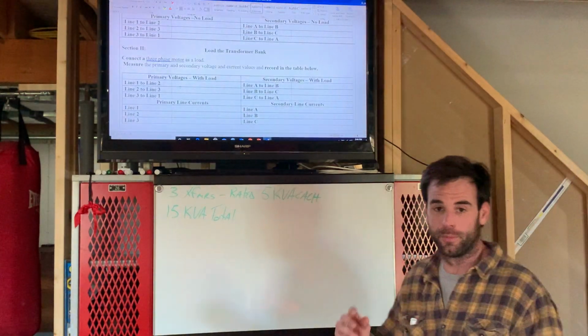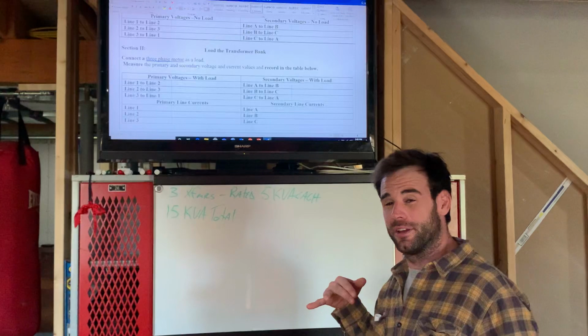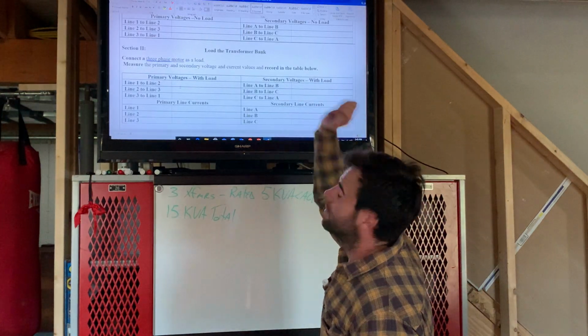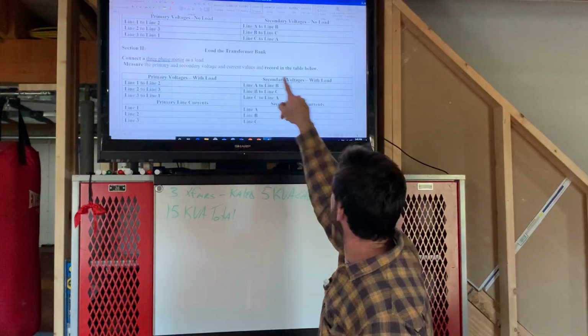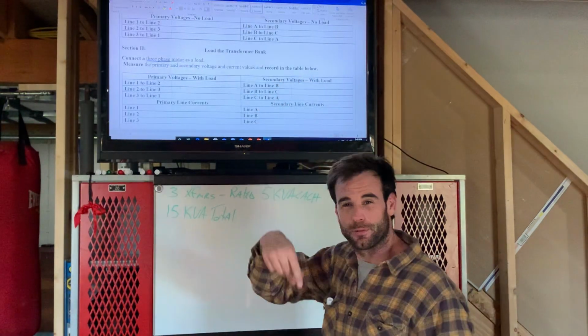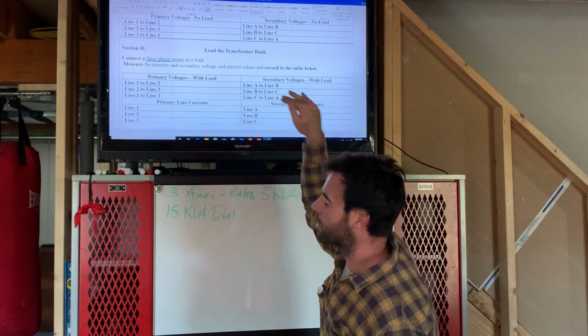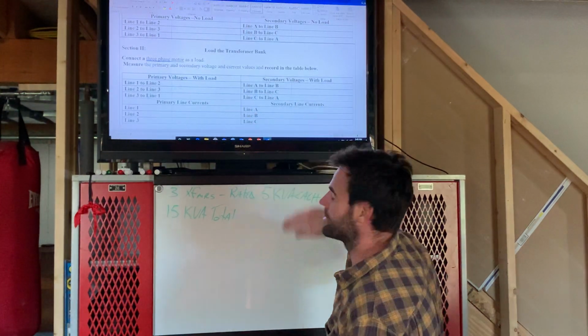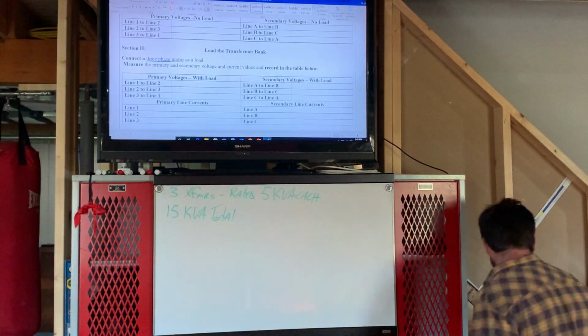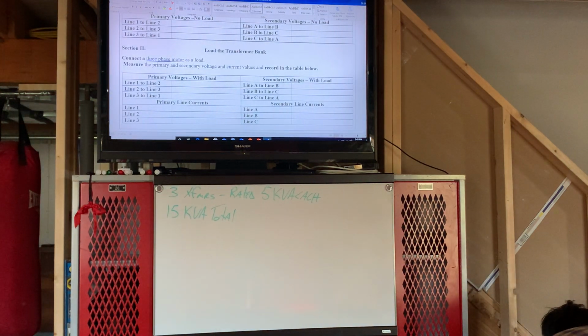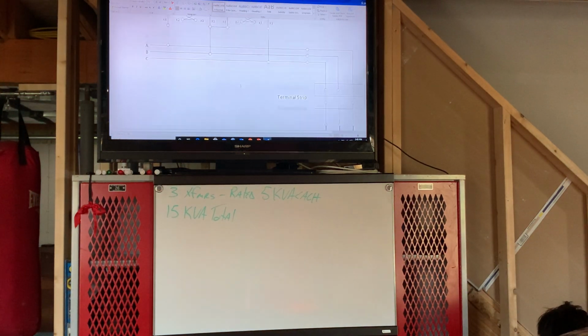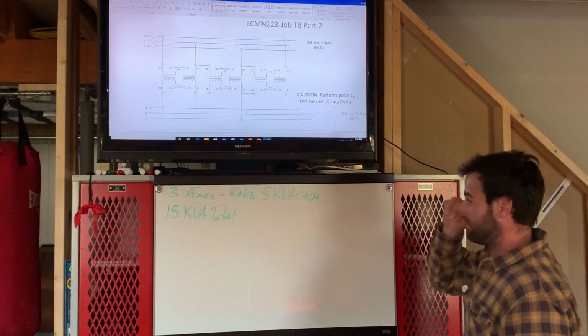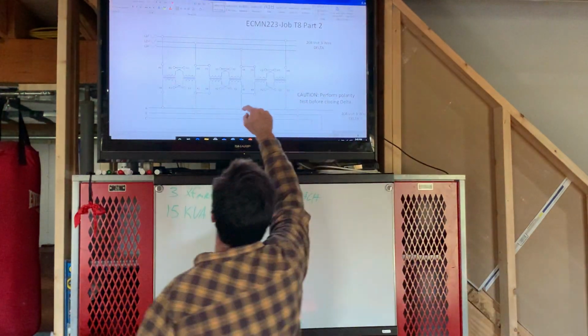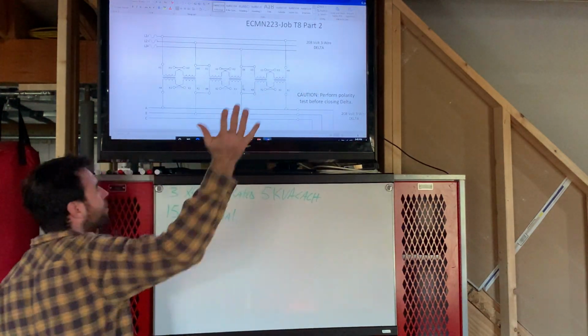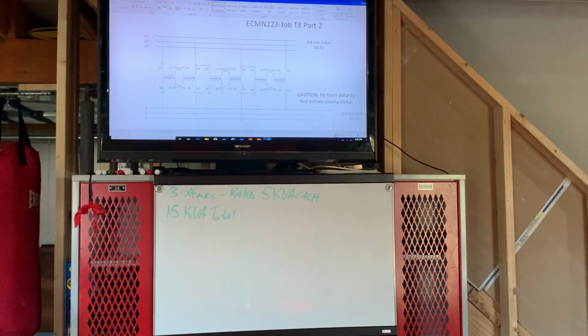and I'm sorry guys, I jumped a little bit ahead. After you close in the delta on part 2, then go through with no load connected, primary voltage readings, secondary voltage readings, connect a 3-phase motor, and then take primary current and voltage readings with the motor connected, and the same thing on the secondary. So that connection, here's my cursor. That looked like this. Let's just say that each of these transformers, 1, 2, and 3, are each rated for 5 kVA each, 15 kVA total.